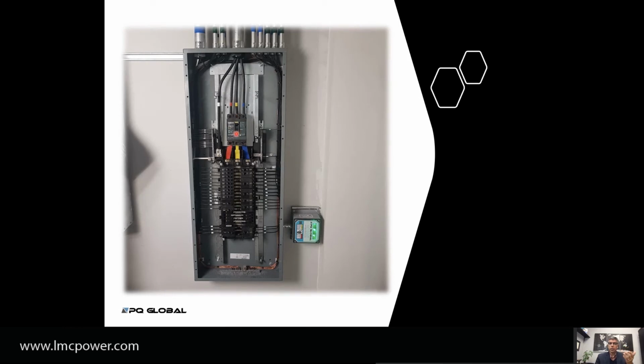Breakers, especially thermal breakers, require heat. They require current to pass through for a certain amount of time before they can even notice it. So transients will go right through breakers without the breakers noticing anything. Now, why do we put the surge protector right here, close to the ground? The transient goes into the panel, and it sees resistance, resistance, resistance everywhere there's load, except it gets to a point where there's a temporary short circuit to ground. A big surge of energy will come into the panel and find its quickest way to ground, where the MOVs create a temporary short circuit drain to ground. So that's where the energy goes. None of the equipment connected to the panels will ever see any of the transient if the surge protector is connected properly.